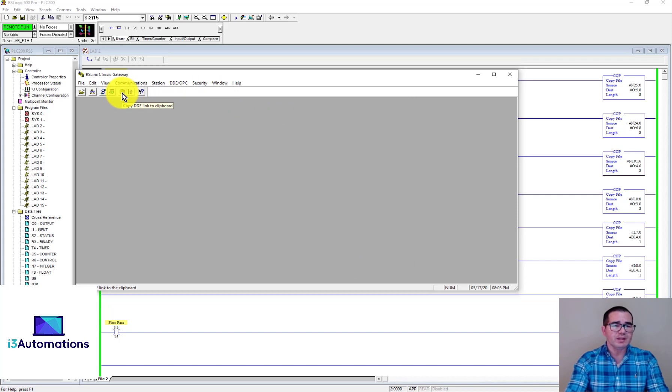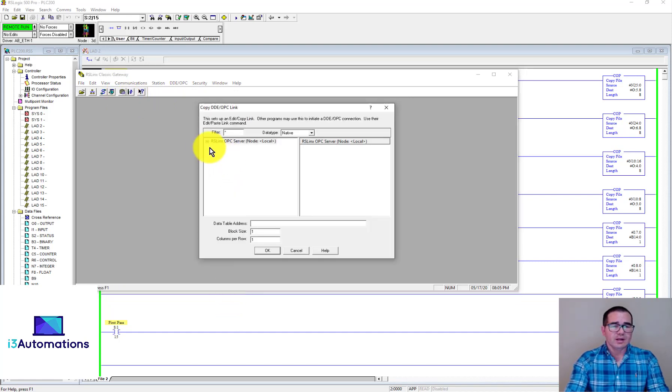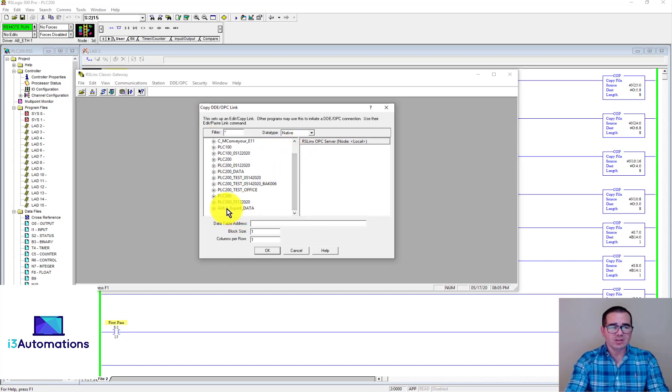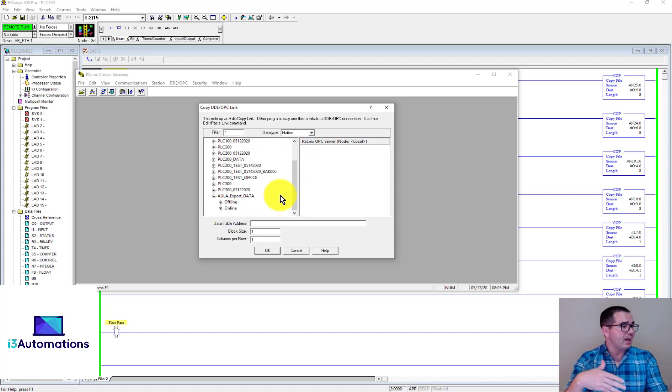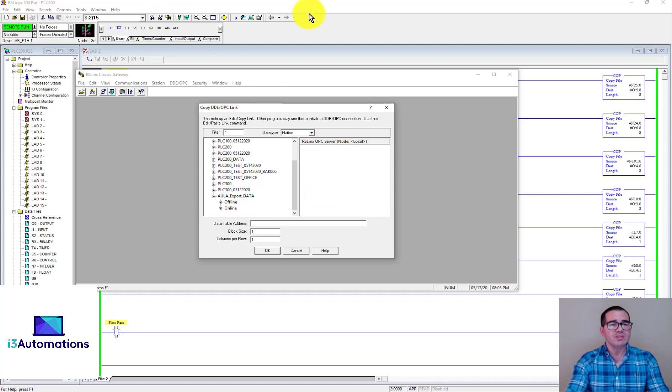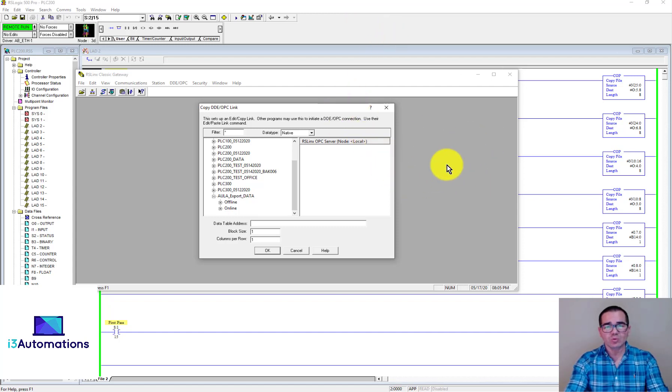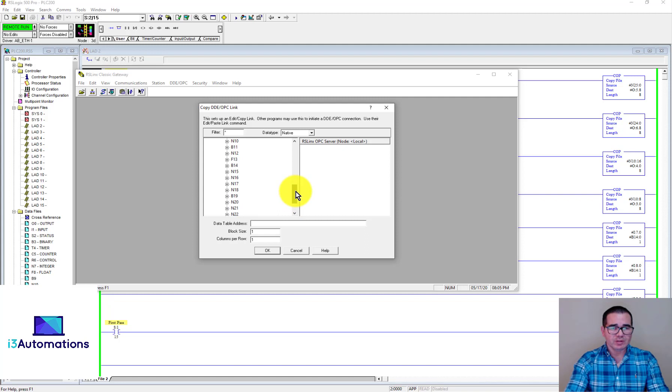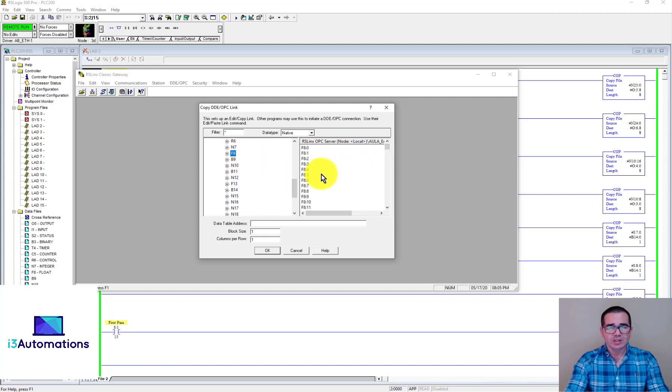Now I'm gonna go to the clipboard, copy DDE link to clipboard, and you can choose what tag you can move to the Excel or CSV file. This is the topic that we created. Now we need to go online. In my case here I'm gonna choose the F8:6 because I know this is the tank level, so I'm gonna choose this one.